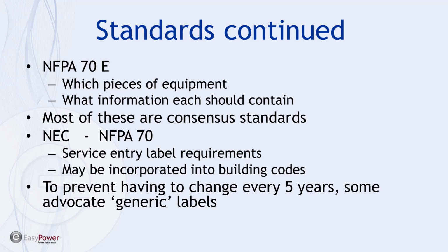The NEC, the National Electric Code, has some specific requirement for service entry labeling if it does not have a standard arc flash label already. And this falls into the category of mandatory in the case where you have to apply for building certification or building permit sign off. And so it's something that's actually in some places codified in the local regulations.